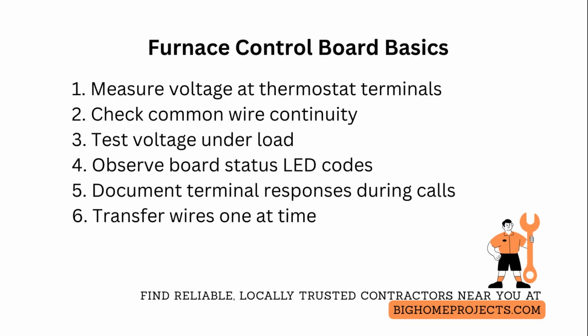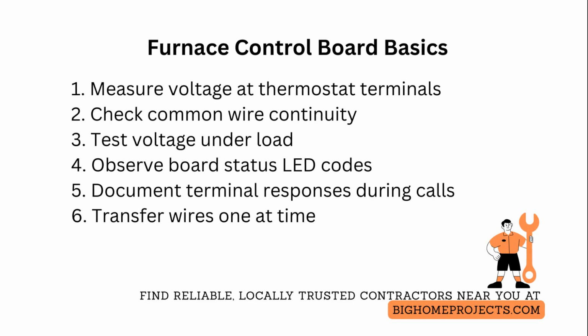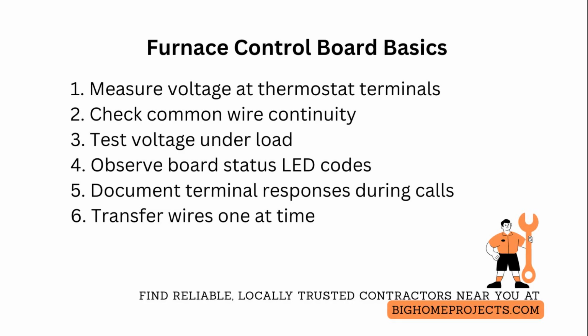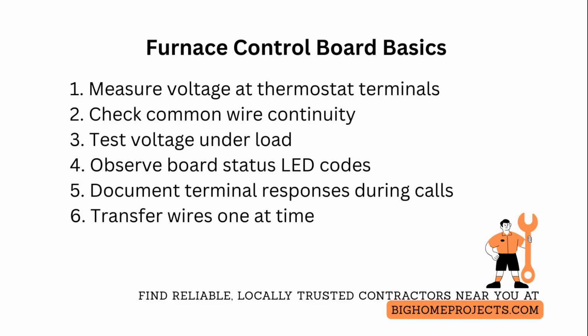When replacing a thermostat, always measure voltage at the thermostat terminals on the board to confirm a stable 24-volt supply before connecting the new device. Check for proper common wire continuity and voltage under load. A board that shows 24 volts open circuit but collapses under load indicates a failing transformer or shorted output driver.